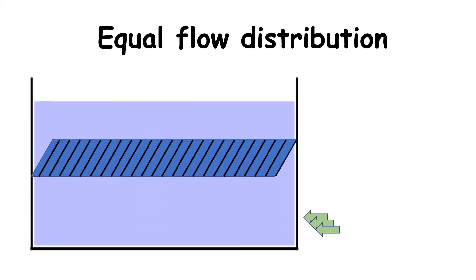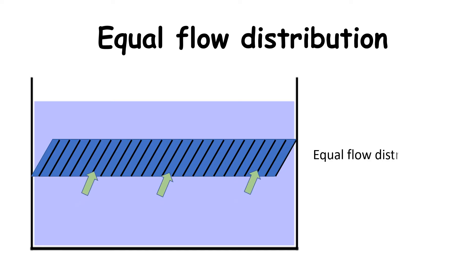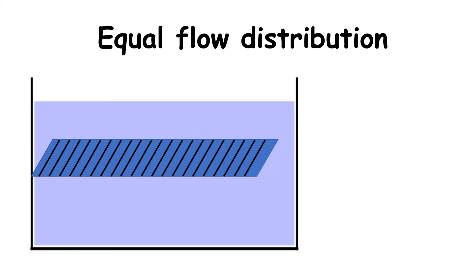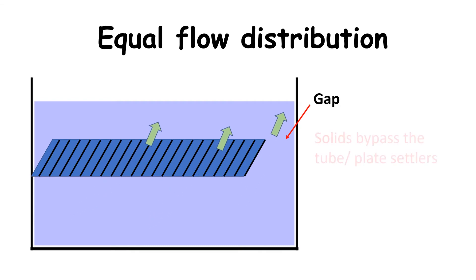Equal flow distribution is very important for both tube settlers and plate settlers to ensure that 100% of the added clarifier capacity is used and not bypassed. Larger gaps in tube settlers or plate settlers can cause short-circuiting of flow, so the solids bypass the settling areas and are carried out with the effluent.